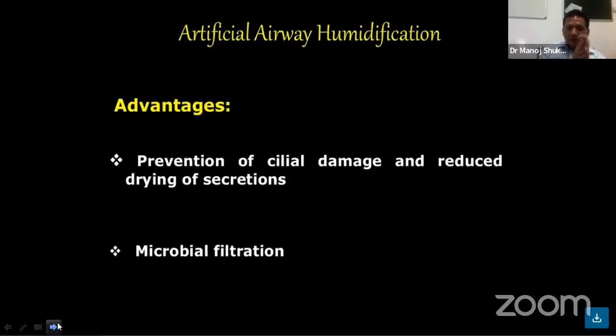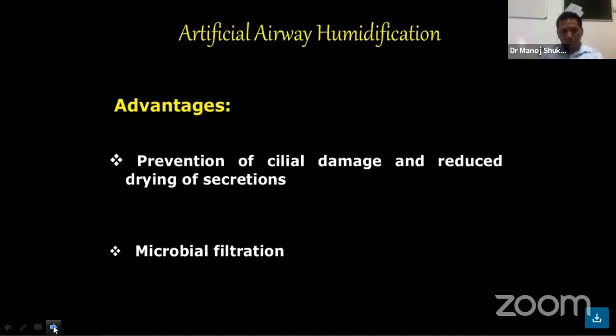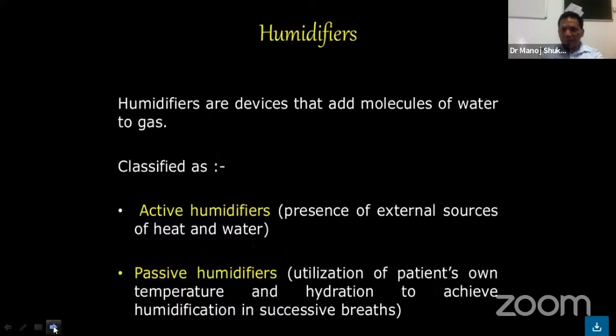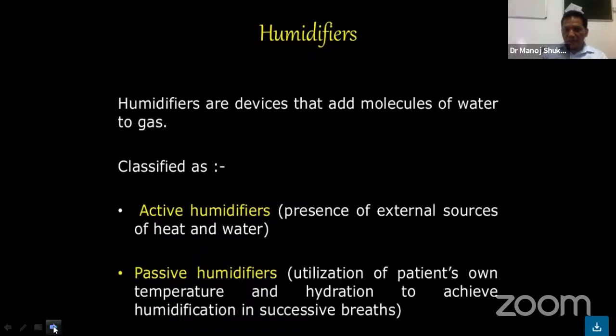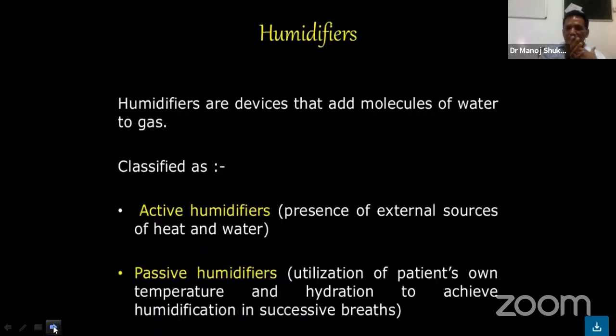In assisted ventilation patients, artificial humidification has advantages which prevent airway damage and reduce dry secretions, and is also helpful in microbial filtration. Basically, humidifiers are devices that add molecules of water to gas. They are classified into two types: active humidifiers, which use an external source of heat and water, and passive humidifiers, which utilize the patient's own temperature and hydration to achieve humidification.